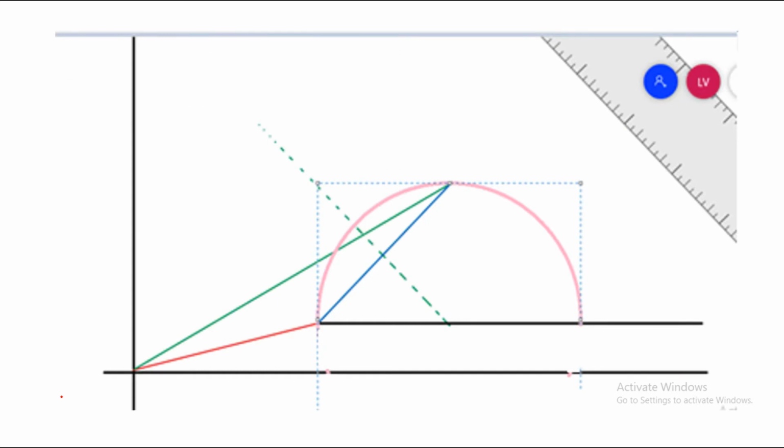Now we'll see the actual circle diagram after obtaining the required data by conducting suitable tests on the three-phase induction motor. We know we have to conduct the no load and blocked rotor tests on the three-phase induction motor for drawing the circle diagram. From the no load test we can get the no load current along with the phase angle phi naught. From the blocked rotor test we can get ISC, but after taking some ratio we can get the value of ISN and also phi SC.